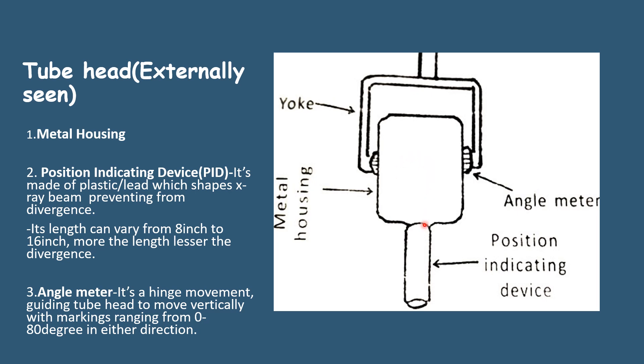This is the metal housing. The position indicating device, or PID, is made of plastic or lead. PID shapes the x-ray beams, preventing them from diverging. The greater the length of the PID, the lesser the divergence. The length can vary from 8 inches to 16 inches. This is the PID.